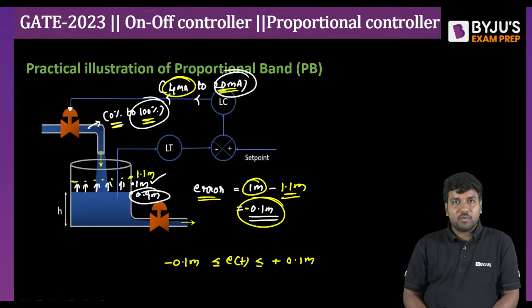Then immediately the water level will come down, right? So when the water level is coming down slowly, now it will take the return here. Now when it is taking the return here, again at 0.9 meter, what will happen? Again the controller output will become 4 milliampere, right? Sorry, 20 milliampere here, and again 100% opening will come and the flow rate is going to increase. That will actually increase the water level.